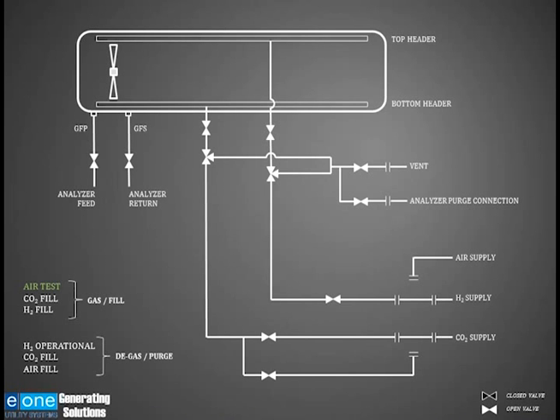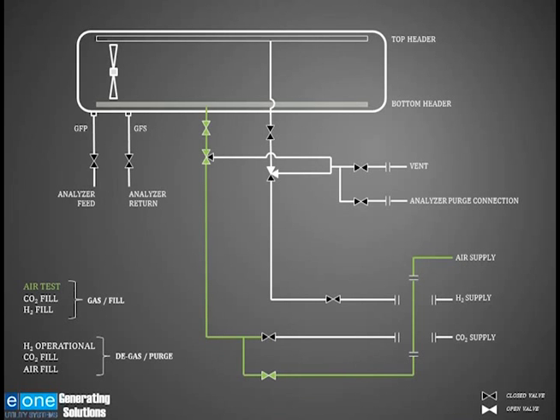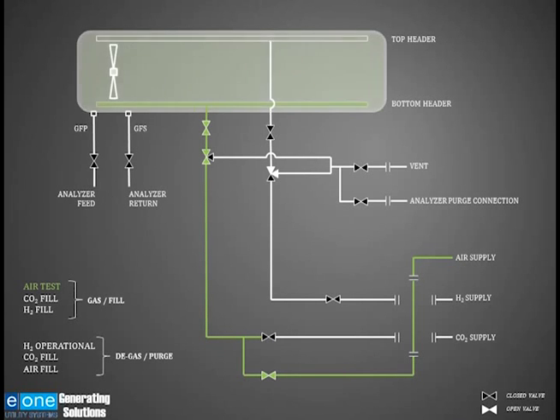So I'm going to connect my air supply over on the right-hand side, lower right-hand side. I've got the valves open so that I can put air in the generator. Now I'm putting air in the generator. This one is now coming through the CO2 header, the bottom header.